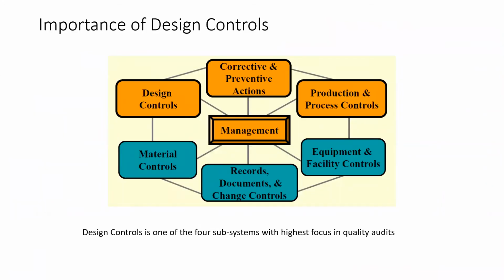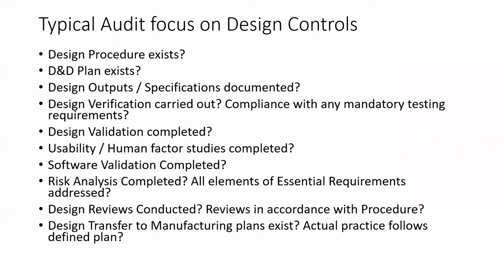Last couple of slides before we move to questions. Why is design control so important in medical device and healthcare? Out of the various subsystems of an organization which are the focus of quality audits, design control is one of the 4 subsystems which have the highest focus. Any auditor who comes and visits you is first going to look at your design control.